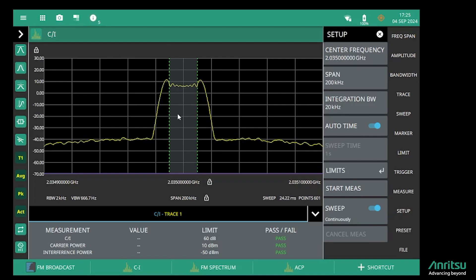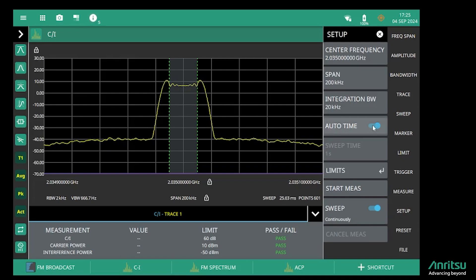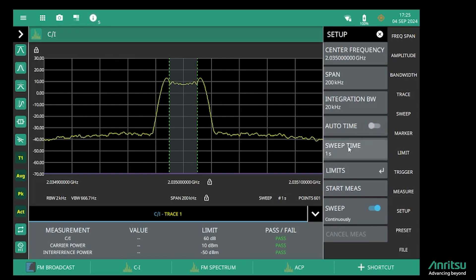When measuring interference, very often it's a pulsed or intermittent signal, so it's often a good idea to set a slightly slower sweep time. That could be as long as a minute if you've got interfering signals that are very intermittent, to make sure that they're captured in the measurement.